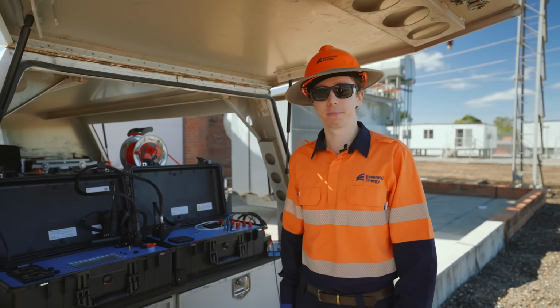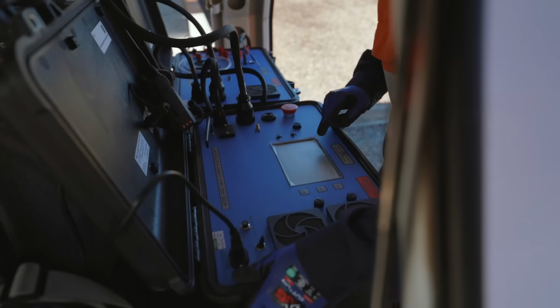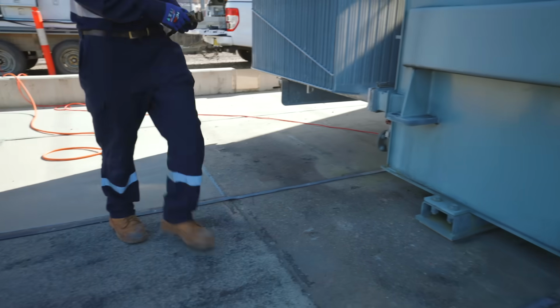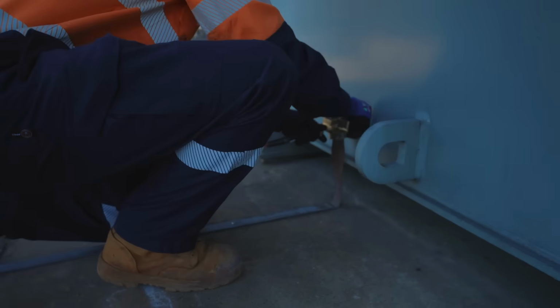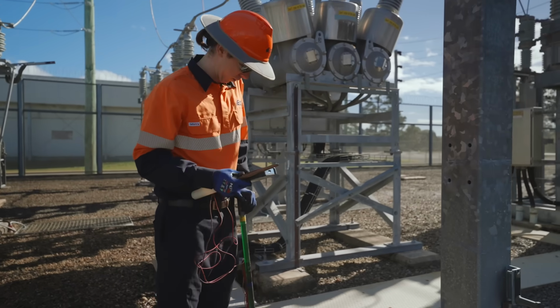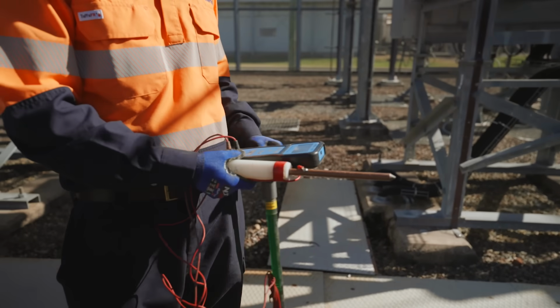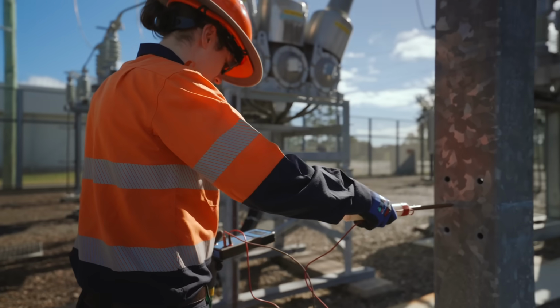With this equipment here, we're testing the earth grid, which is made up of bare copper conductors laid underground. That provides a low impedance path for fault current and also maintains the potentials around the yard at a stable and acceptable limit.